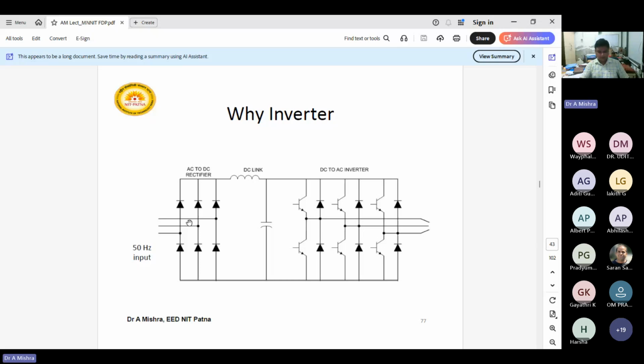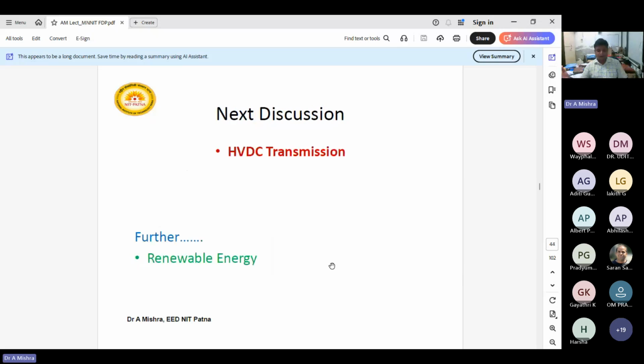On the front side, there is a rectifier. It will convert the grid supply into DC. There is a DC link. Then there is an inverter. What is the advantage of this? This is not new to any electrical engineer. But here, the first advantage is that I am able to control both voltage and frequency at the output end, whatever the requirement. Another important thing is that any small fluctuation on the input side will not disturb my output, because I have the DC link, and based on the fluctuation level you can choose the capacitor size. If the capacitor size is sufficient, then any small fluctuation in the input voltage will not disturb my output voltage of the three-phase requirement, that is, variable voltage, variable frequency.